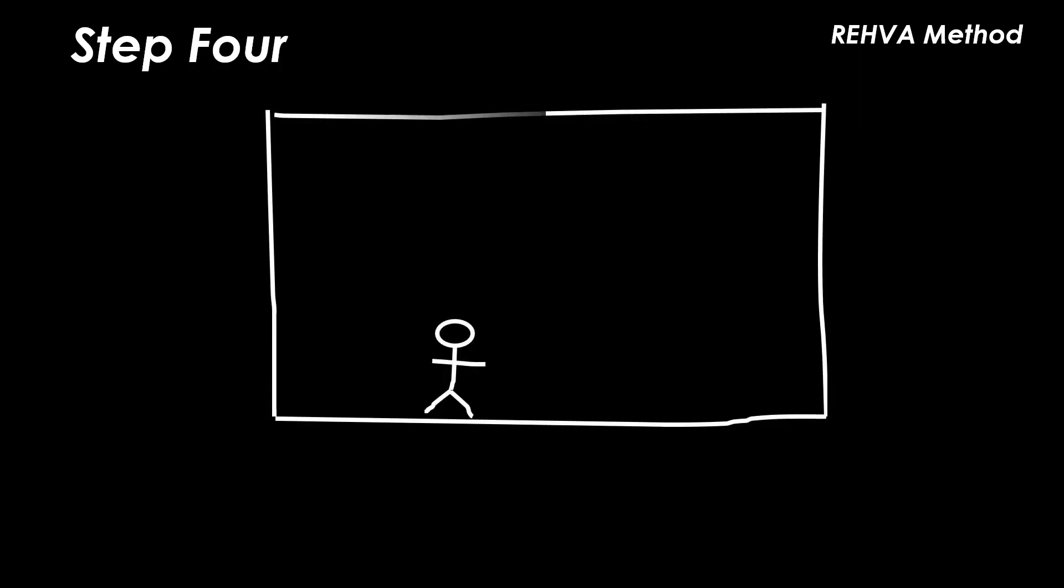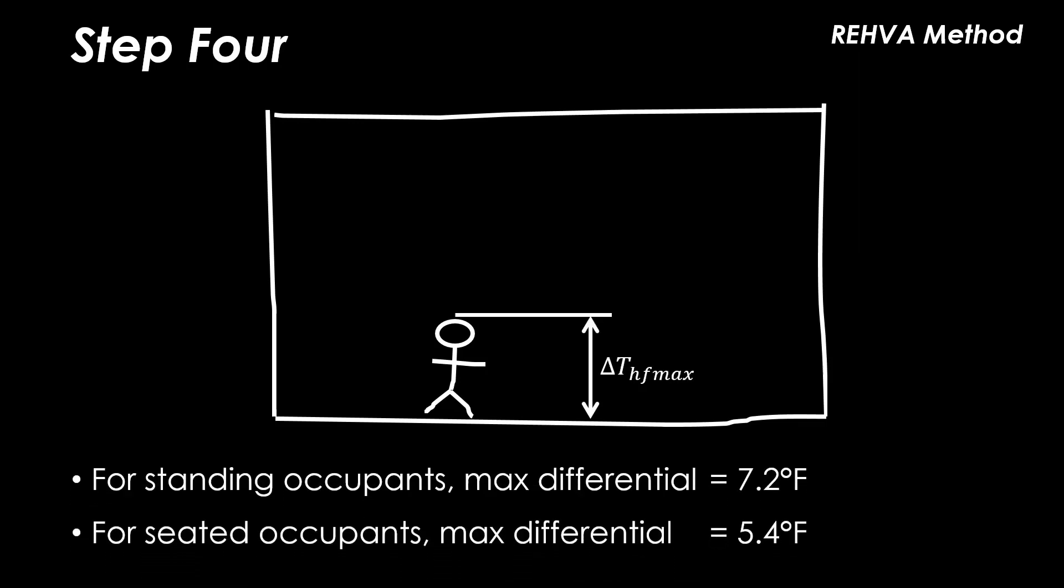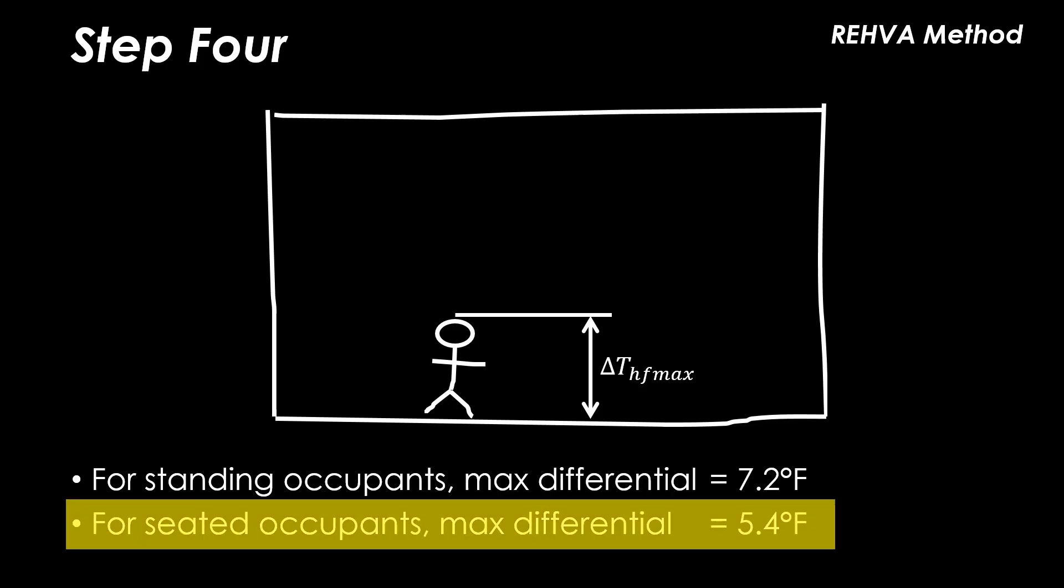In step four we must determine the maximum allowable temperature gradient, Delta THF Max. This is the vertical temperature difference between foot and head level. Note that a high differential could result in discomfort. ASHRAE Standard 55 2017 can be used for guidance but for standing occupants a 7.2°F differential is recommended and for seated occupants 5.4°F.